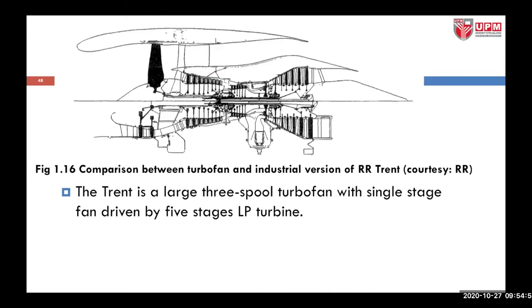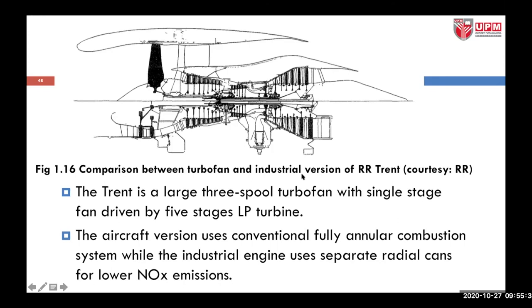This is a comparison between an aircraft turbofan and the industrial version of a Rolls-Royce Trent engine, since this type of engine is installed in both aircraft and land-based applications. This Rolls-Royce Trent engine is a large three-spool turbofan with a single-stage fan driven by five stages of low pressure turbine. The aircraft version uses a conventionally fully annular combustion system, while the industrial engine uses separate radial cans.